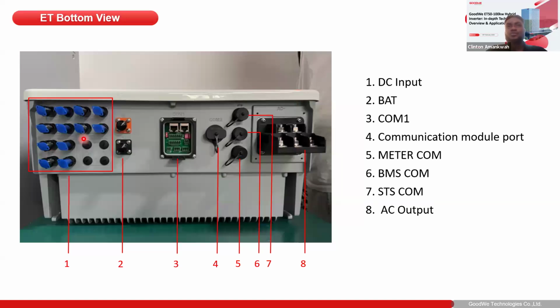The inverter also comes with, so the 40/50 kilowatts comes with 150% DC oversizing. With this, you get to oversize your hybrid system on the panel size. The main idea behind this DC oversizing is just to allow you to get full load operation and also still get excess power to charge your battery. In terms of current ratings, we have a maximum of 42 amp DC input current on the MPPT side, and a maximum voltage of 1,000 volts.